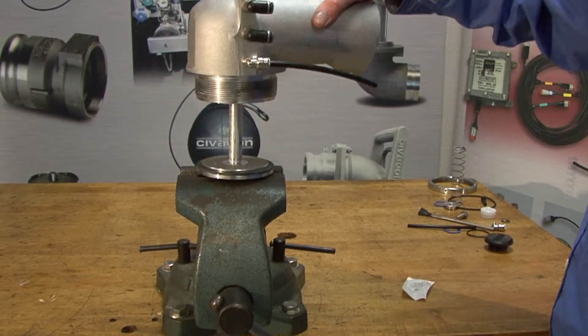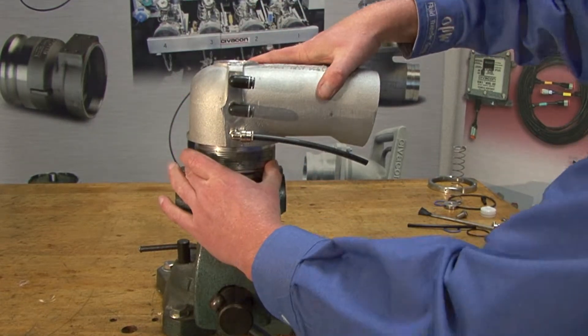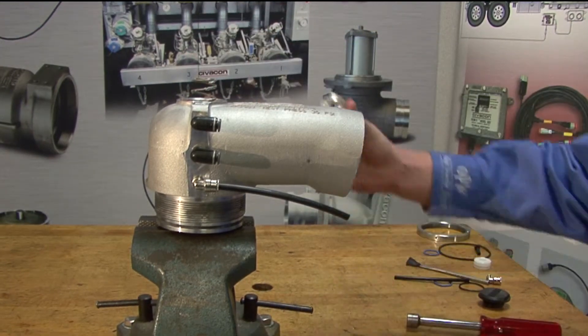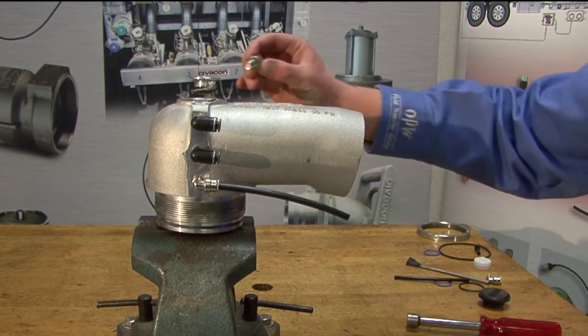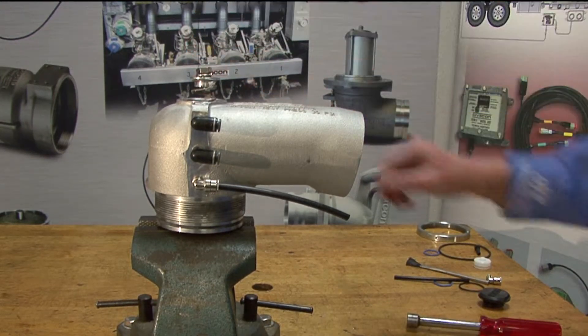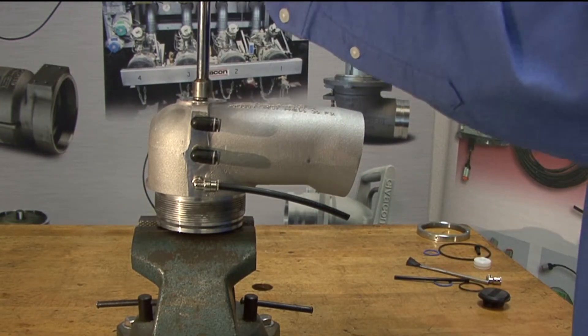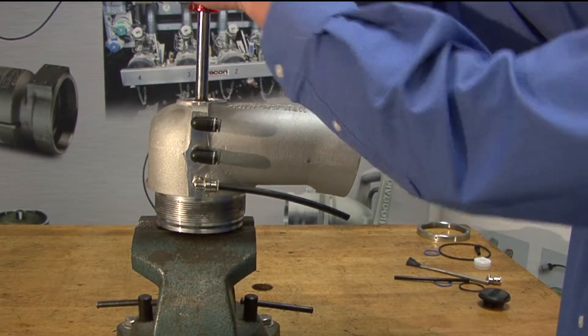Attach the vent body to the poppet. Insert the new poppet spring, spring guide, and lock washer into the shaft bore. Using a 9/16 socket wrench, gently press the poppet spring into the shaft bore and tighten the bolt to 22 foot-pounds.